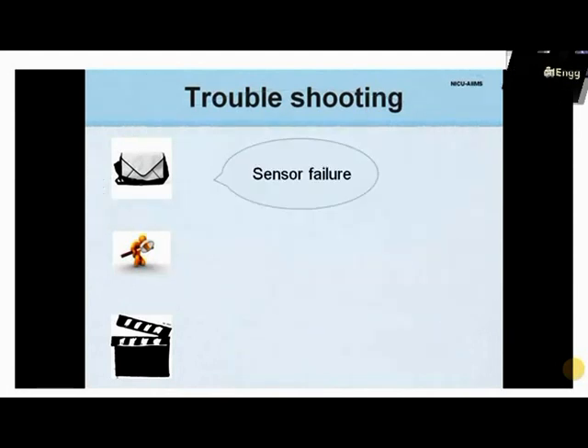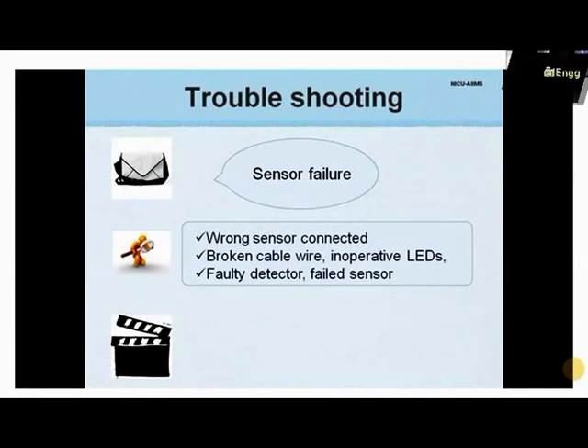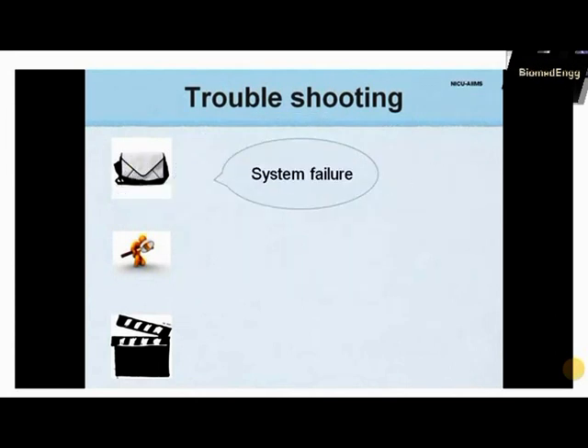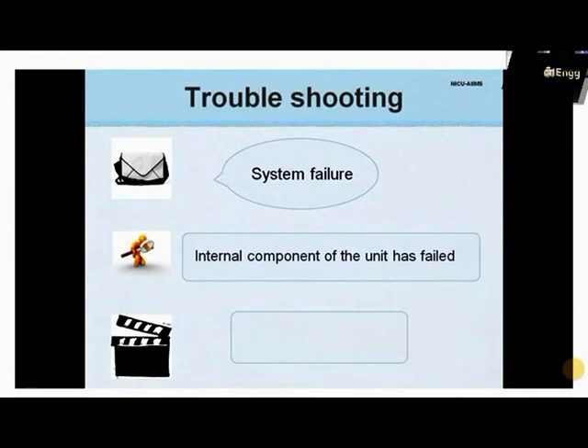A sensor failure message is serious, as the causes could range from a wrong sensor, broken cable wire, inoperative LEDs, or faulty detector to a failed sensor — the solution is replacing the sensor. When there is a system failure message, some internal component of the monitor has failed and the entire unit requires service.